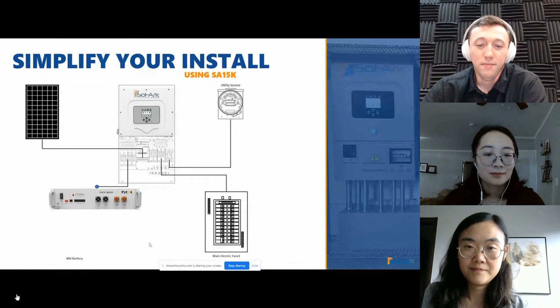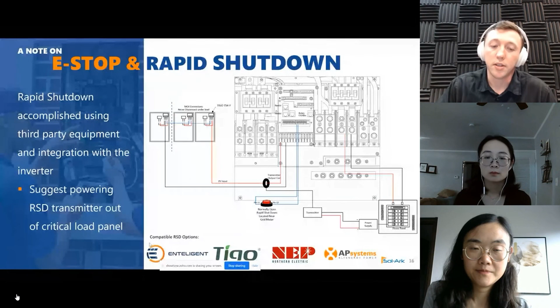Just a note on rapid shutdown: it's a requirement for the National Electric Code. If you're ever doing roof mounted panels, you're going to have to install rapid shutdown with most inverter systems. What we can do is actually tie in rapid shutdown devices from companies like Enteligent, Tigo, NEP, or AP Systems, and they'll tie directly into our Sol-Ark inverter. Sometimes we can even tie in the rapid shutdown transmitter at our 12-volt input, so that can help you out there. Otherwise, here's just a small example of a rapid shutdown connection and how it integrates into our inverter. Feel free to talk to our engineer team on how to integrate those products and how easy it is.